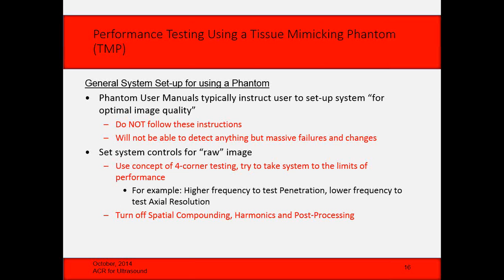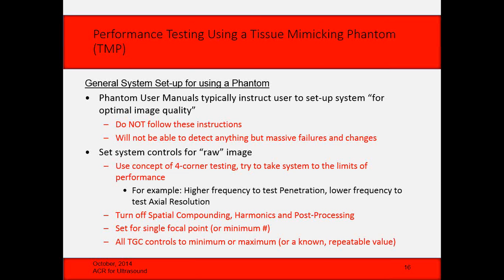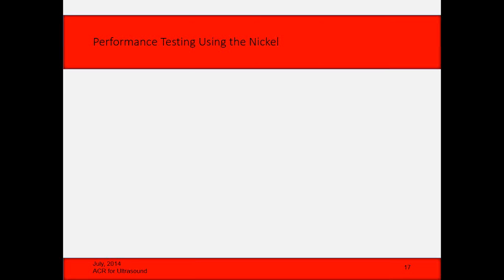And then, because you need to be able to repeat this in the future, you need to set all the time gain controls, the TGCs, to either minimum or maximum, and you'll figure out pretty quickly what it needs to be on the system you're working on. Like GE systems, it's usually all maximum. Philips systems, it's all minimum, if I remember right, and the Siemens systems kind of vary, but you'll figure it out. If you can't adjust the gain far enough to do your test, then you know you need to go to the other end. But you need to be at a known repeatable value for the TGC controls, so when you come back in 6 months, or if they call you in because they think something is broken, you can repeat the exact same test with the same presets, the same settings of the system, same depth, everything, so that you're repeating the same test again.